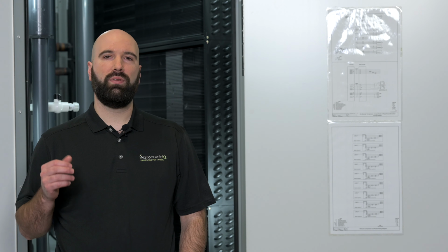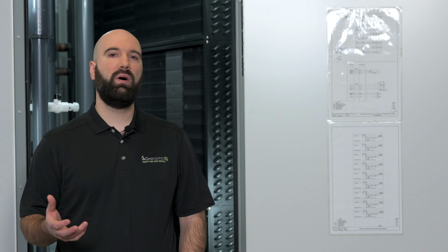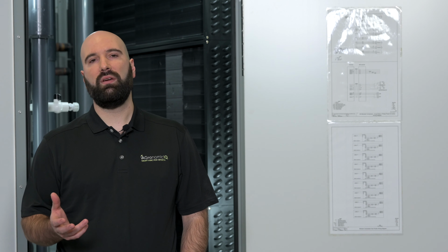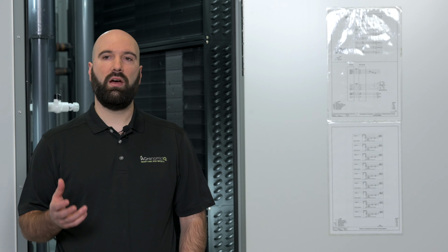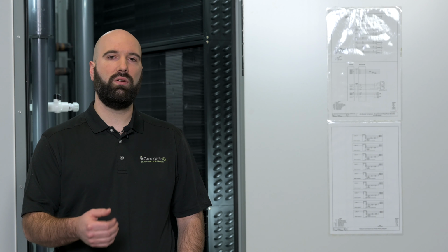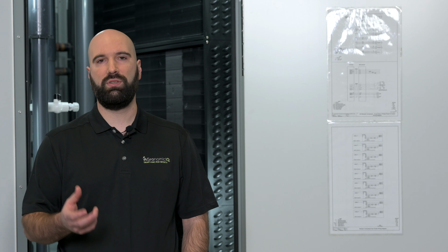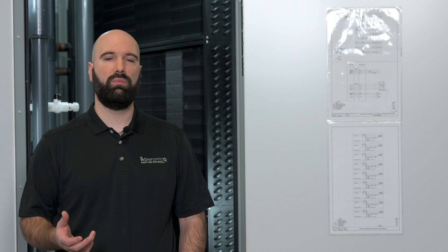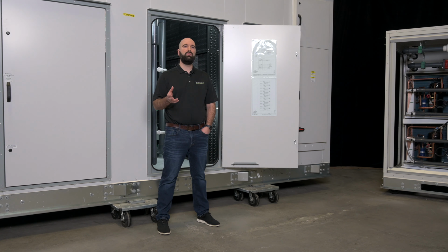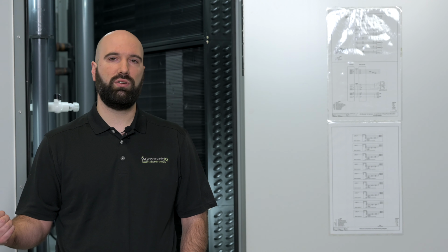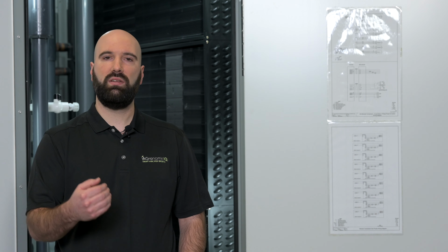In this section behind me, we've got both the compressor pods, the hydronic reheat coils, and the pump to make the whole system work. Now, one of the brilliant things about the compressor wall technology is our reliance on a hydronic loop for both heat rejection and for the reheat coils. And it's really the reason we're able to do multiple small circuits in a cost-effective and controllable way. By dumping all of the compressor waste heat into that hydronic loop, we're able to fully modulate between the reheat coil and heat rejection outside and achieve 100% heat rejection to either the process air stream in reheat or dehumidification mode, or outside to the dry cooler in air conditioning mode, or proportionally between those two. And that allows us to achieve a very, very tight space temperature control.